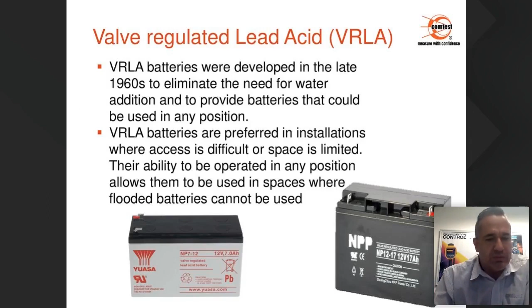VRLA batteries are preferred in installations where access is difficult or space is limited. Their ability to be operated in any position allows them to be used in spaces where flooded batteries cannot be used.